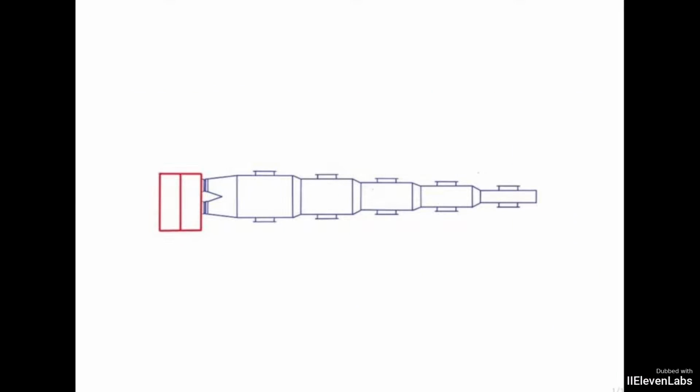So in our example, we are going to use a 10 TR equipment. In this case, it's a standard large split installed in the horizontal position. The nominal flow rate for this equipment is 6,800 cubic meters per hour, okay? This flow is a common flow for any manufacturer.